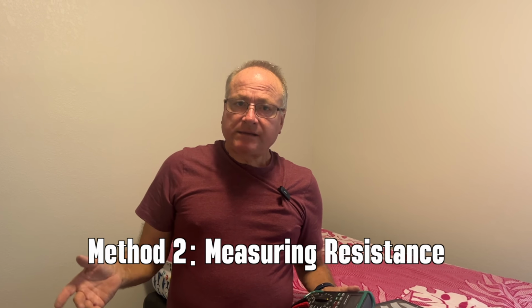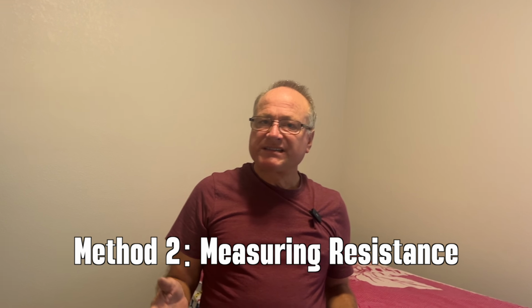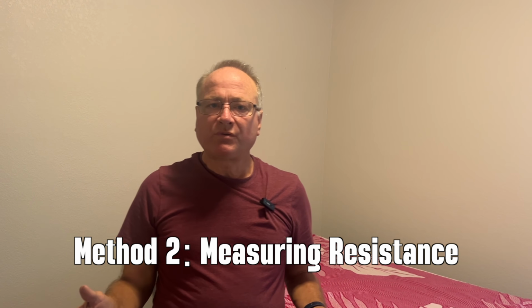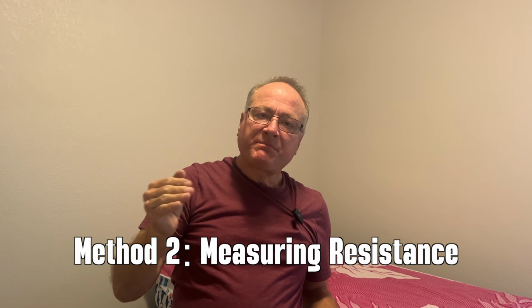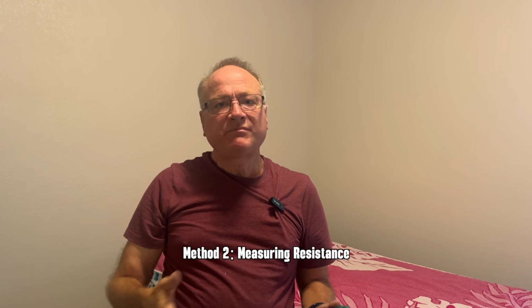This second technique involves measuring the resistance between the ground and neutral wires. The further you get from the panel, the more resistance you'll have, because there's more wire. So we're going to measure the resistance at each of these receptacles.